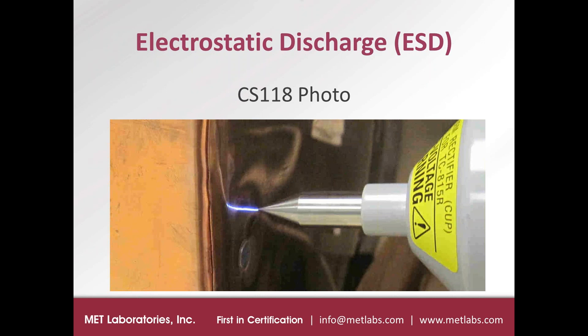This is just a photograph, very close-up, of the tip of an ESD generator as it's discharging to a copper wall. The full generator, if we could see a zoomed out view, looks kind of like a toy gun. It has a handle with a trigger, and it allows for two different tips to be connected. So this is the contact discharge tip, which is pointed. For the purpose of the photograph, just to see the arc, it's not touching the surface, but when you're doing contact discharge, the tip would actually be placed in contact with the conductive surfaces of the equipment under test.